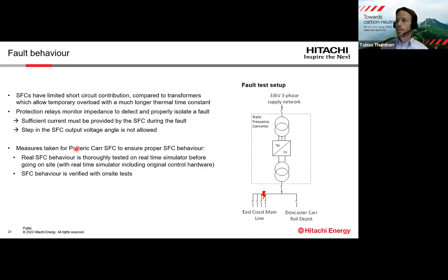Another very important topic is the fault behavior of the static frequency converters. I've mentioned in the beginning that SFCs have a limited short circuit contribution compared to transformers, which usually can easily have an overload of 2-3 times nominal. The SFCs have a much smaller time constant. So this means that they can typically only supply quite a small overload current.